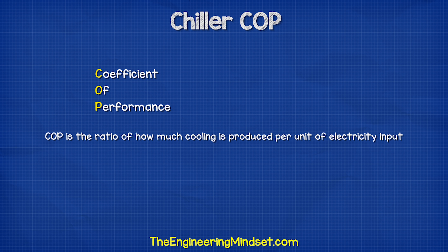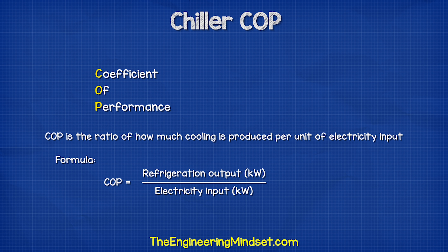Chiller efficiency is measured in COP, which stands for coefficient of performance. The COP is just the ratio of how much refrigeration you get per unit of electricity you put in. The formula is very simple: the COP is just the division of the kilowatts of refrigeration divided by the kilowatts of electricity.